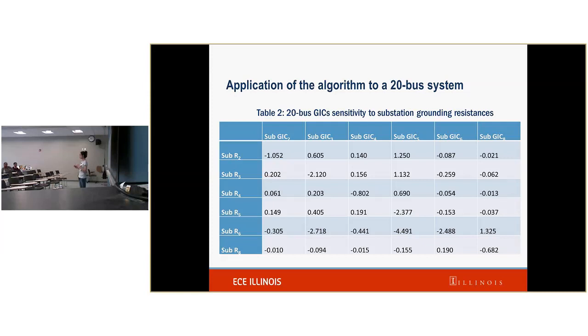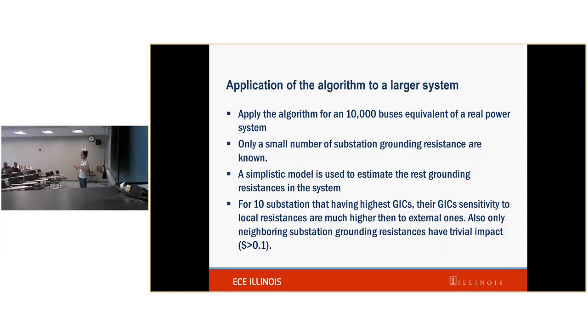The value of 0.01 ohm is actually small. The normal difference can be 0.1 or even 0.5. So if the difference of the resistance is 0.5, then the difference of GIC is almost about 40%, which is big, meaning that the GIC we got is totally different from the real GIC.